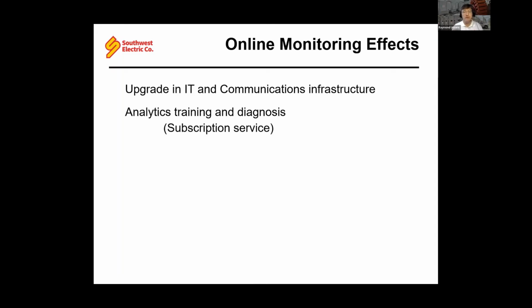It's probably going to be, you're going to ask someone to do it for you, and that'll be another subscription service. And you're going to need flexible shutdowns, because if you start acting on this information, you might find that your primary switchgear might need attention sooner than you expected. You can avoid a major fault or issue, but you're going to need a shutdown to address it sooner than you're going to need a shutdown to address your transformer or your secondary gear. And so therefore, in order to act on the information you're getting, you're going to need some flexible shutdowns.